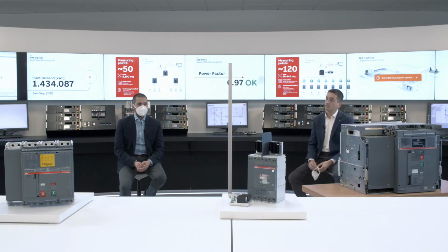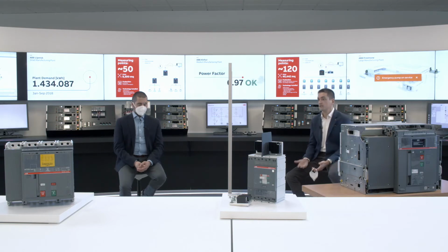Another parameter we have to consider is the speed of remote control we can have. With remote control made by coils, we can have the fastest control possible, and it's not only the possibility to control from a remote point, but also to make it faster than any manual activation. So those elements are very important when we have to choose between a generic switching device and a breaker-based switch or automatic breaker. Auxiliary contacts are very important for service continuity, but another important accessory for service continuity is also the motor control unit.